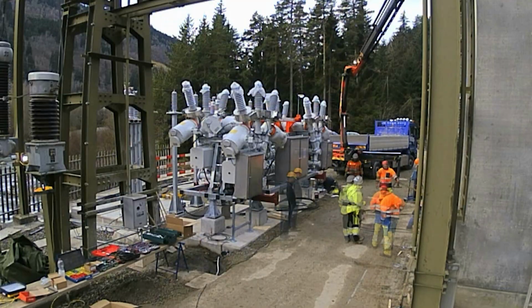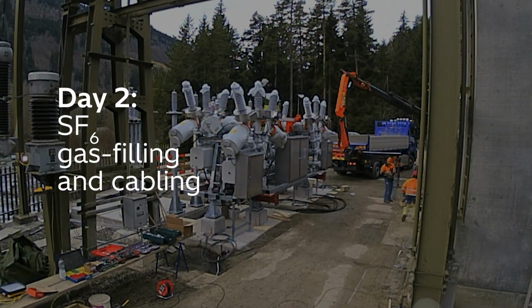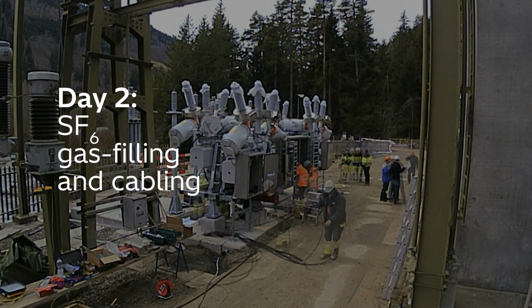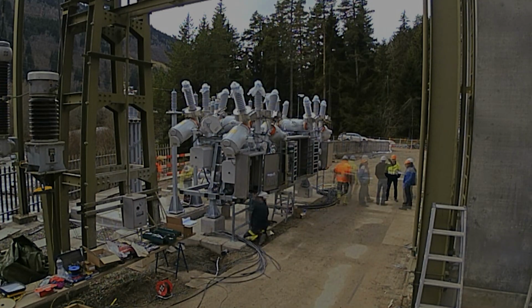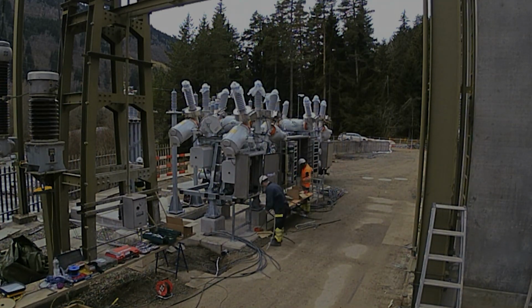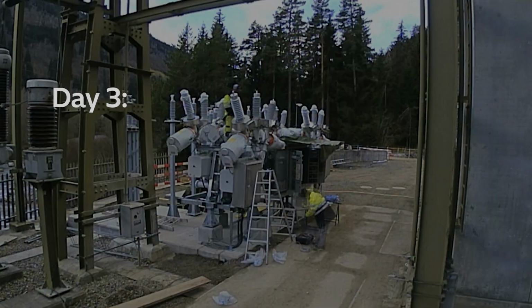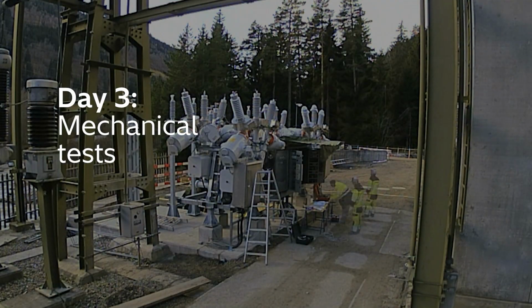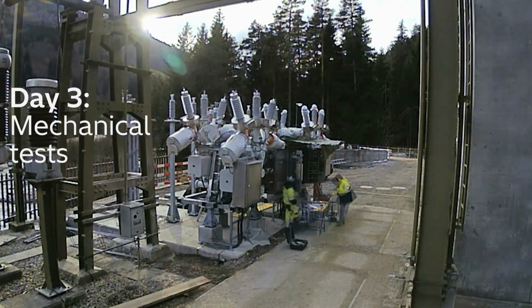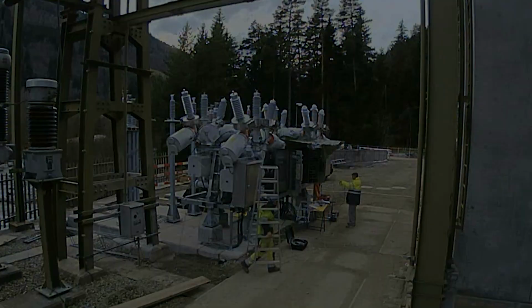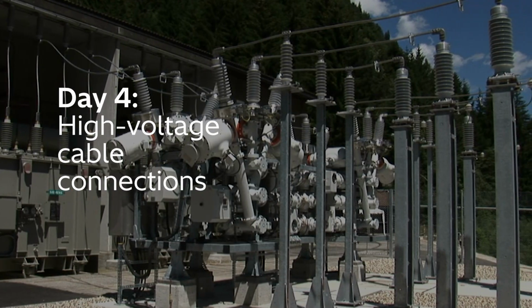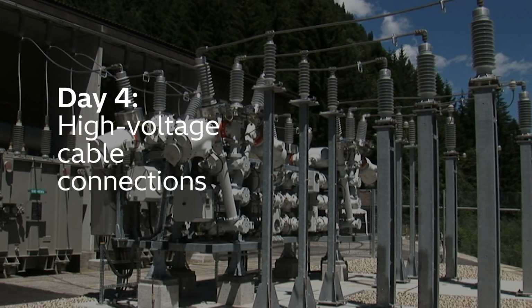The innovative hybrid modules use traditional air-insulated connections between equipment, while all bay functions are enclosed in a single-phase gas-insulated housing. As all the functions of a complete switchyard with an H configuration are configured as a single sub-assembly, the PASS M0H has a significantly smaller footprint than alternative solutions.